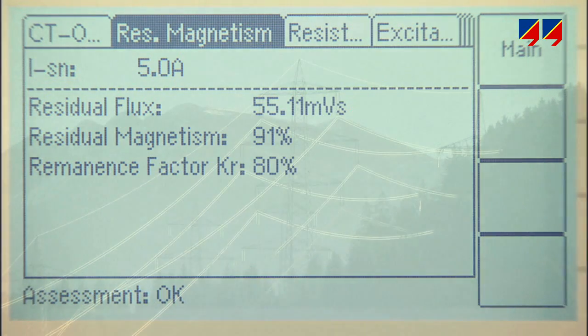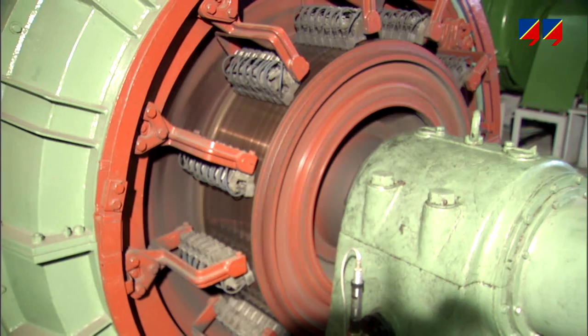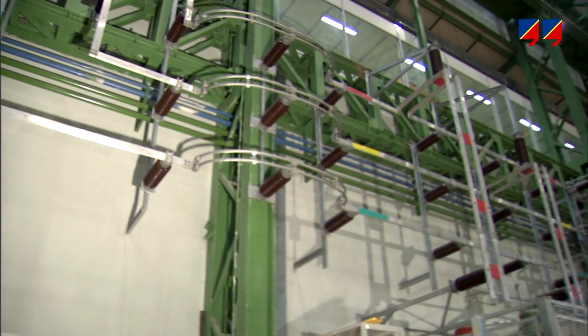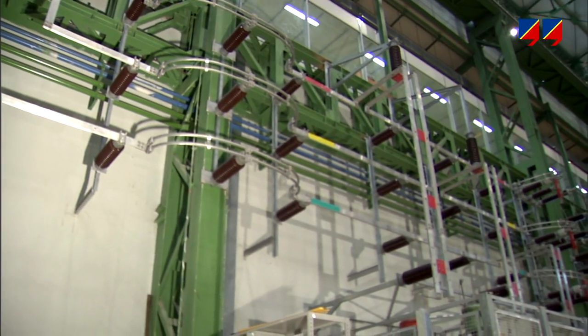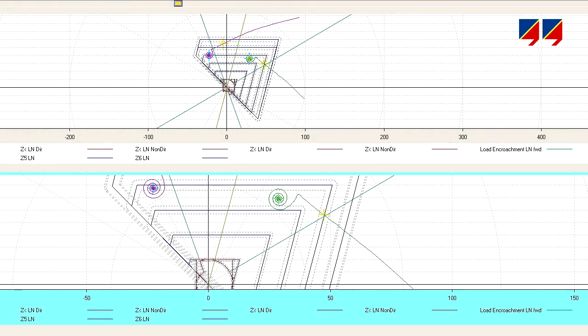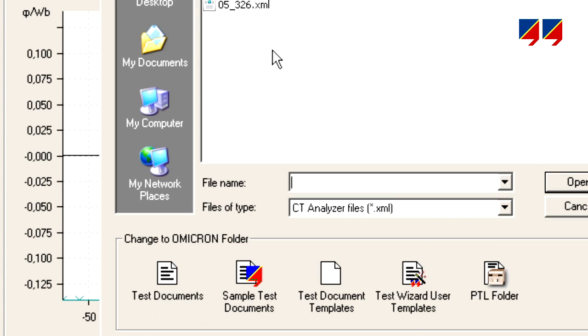Knowing the remanence value is important to analyze a malfunction of an important line, generator, transformer, or bus bar protection — using, for example, a simulation program — or to ensure that the CT will perform correctly in the future.